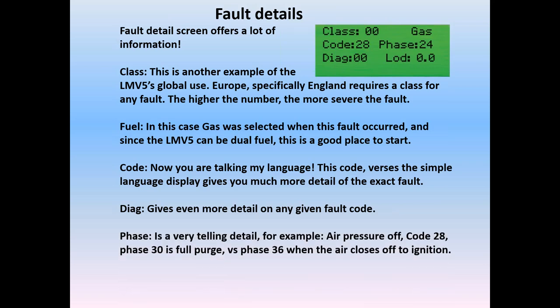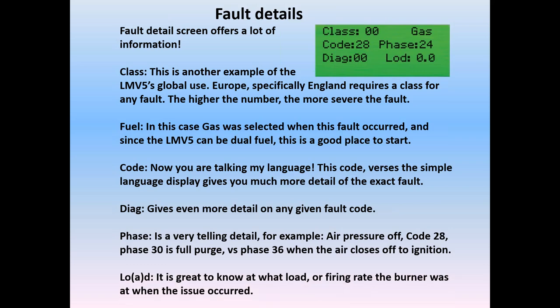Phase is very telling. For example, air pressure off, code 28 — if it was phase 30, we'd have been in full purge, which clearly means the air pressure switch was not connected in any fashion and never makes even when we're in full purge. However, if we had a fault when it went to phase 36, then we know the air pressure switch would have failed when the air damper was driving down to ignition position. That simply means the air pressure setting needs to be adjusted to maintain the air pressure switch even when airflow is reduced for the ignition light off. We also get a load indication so we know what load or firing rate the burner was at when the issue occurred, which also helps diagnose the problem.